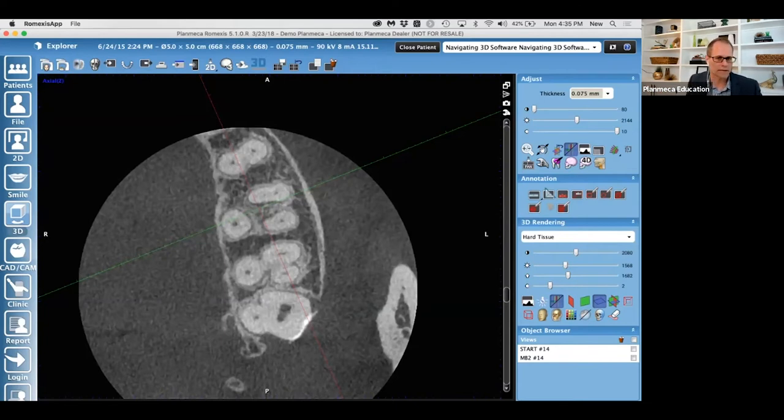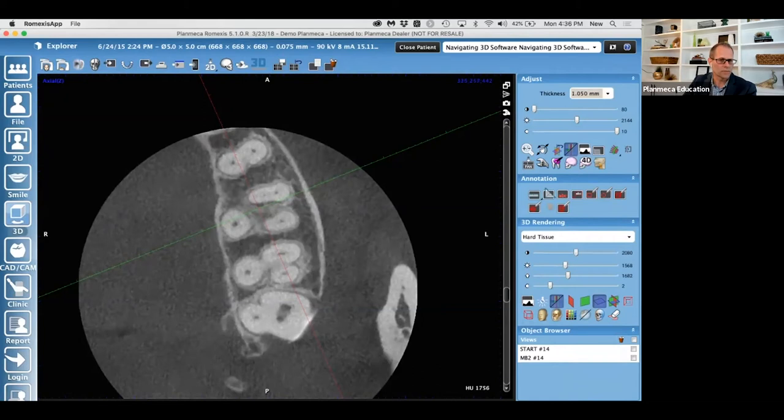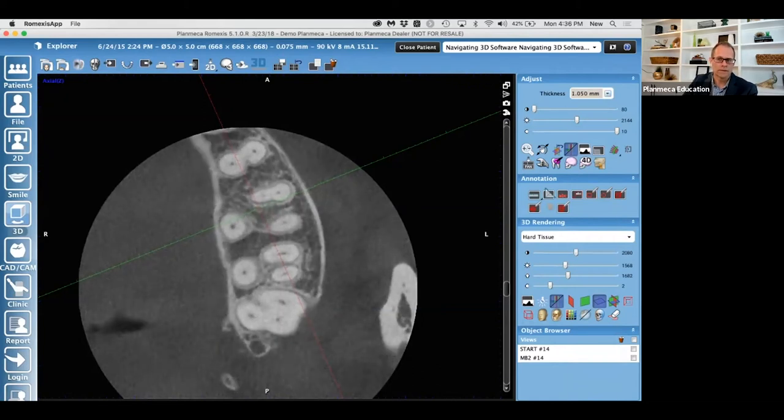The sensor is being more sensitive to lighting. If you've taken photography classes, you'll know what I'm referring to. If I open up that shutter and say, bring it on in, I'm going to cause either a good response or a bad response. So when I'm taking a 75 micron scan, I'm opening up the sensor so it's more sensitive, and I'm driving more radiation through the tube head, creating more photons to that sensor to get a better image quality. The downside is, a thinner slice might not be the best thing for your eye. So feel free to just select a thicker slice, and that might give you the information you were looking for.